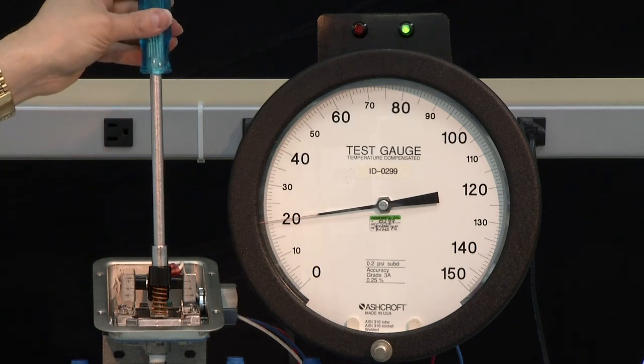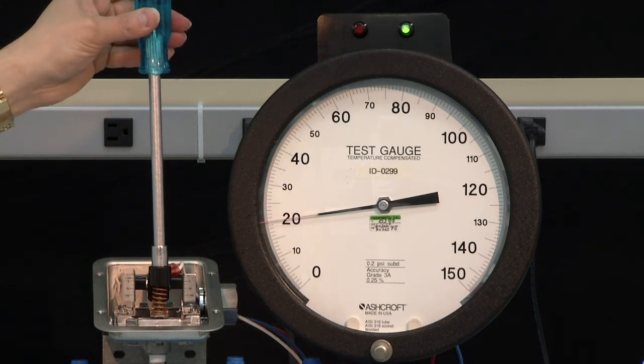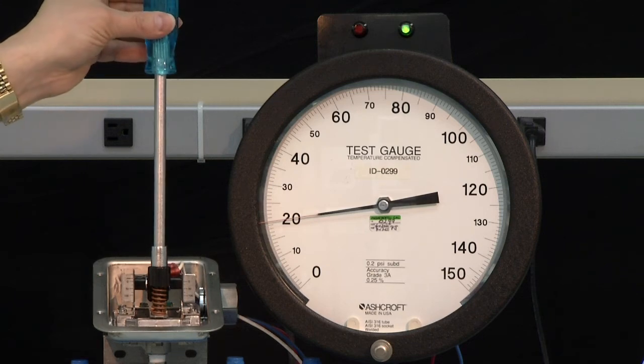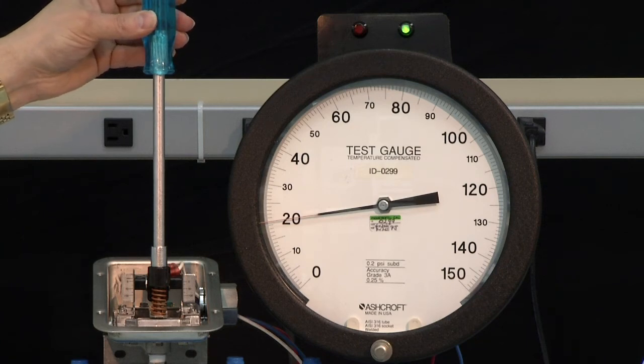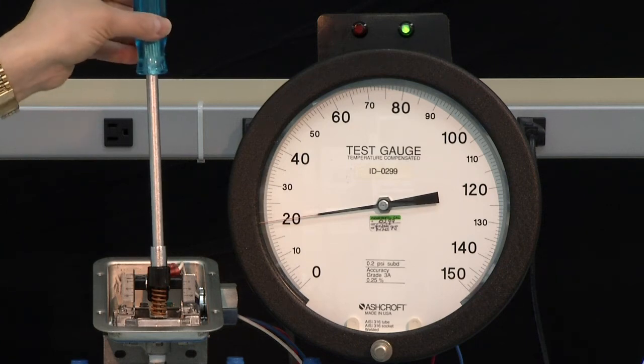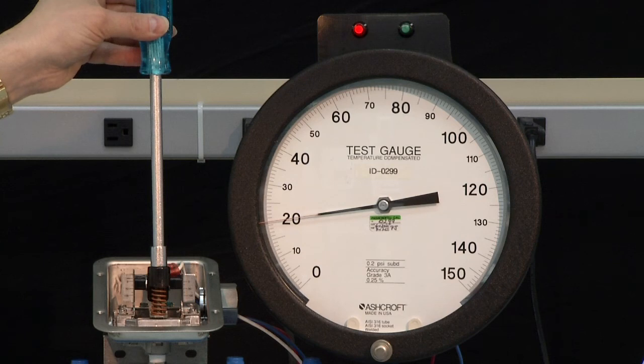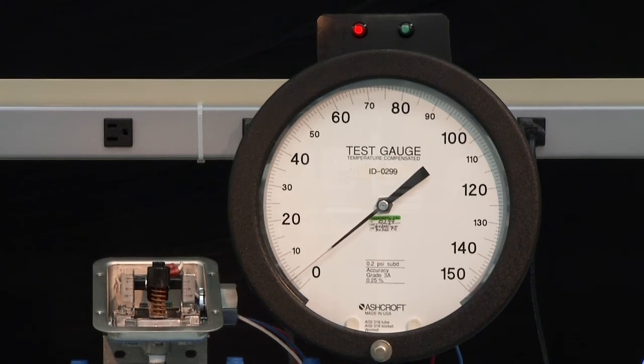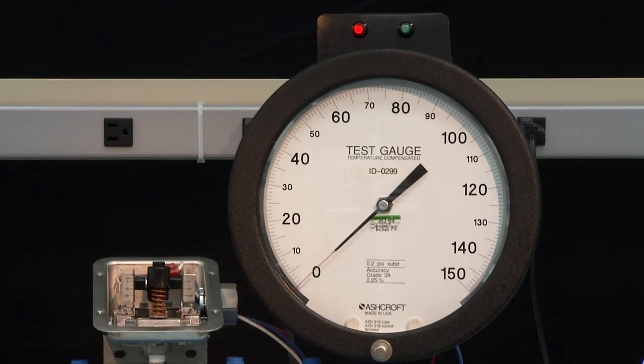Now we're going to turn it clockwise until it just turns off. Now we will measure the set point to see if we have set it correctly. So to do that we will drop it to zero and then take it to 100 pounds. And then we will go down and measure the set point.